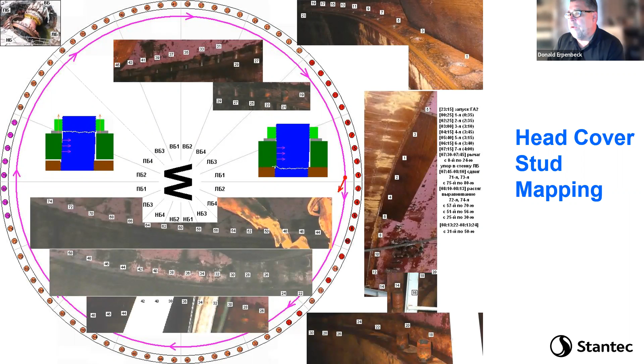Now, one of the things that happens when you trip a turbine off, if you don't have a catastrophic failure, is we close the wicket gates typically in about 10 or 15 seconds to close off the flow. The water tries to separate underneath the turbine as it's going out the draft tube. And then at some point you pull a vacuum and it begins to slam back up and in theory could lift the turbine back up, but it's very rare. And the timing on the wicket gates allows that not to happen. But a lot of current conclusions suspect that's what happened, and that some event like that occurred, and we had a reverse water hammer from the draft tube.